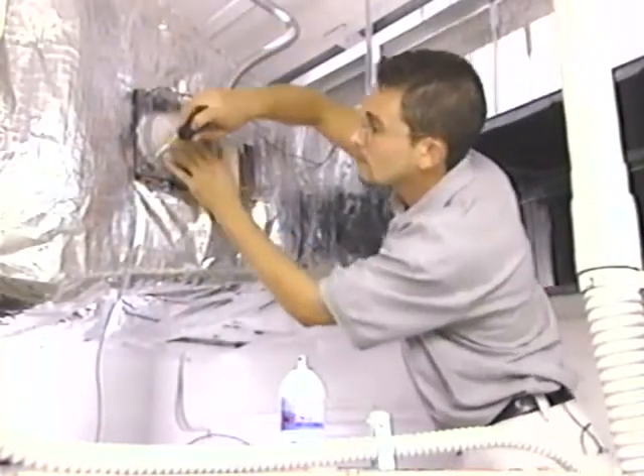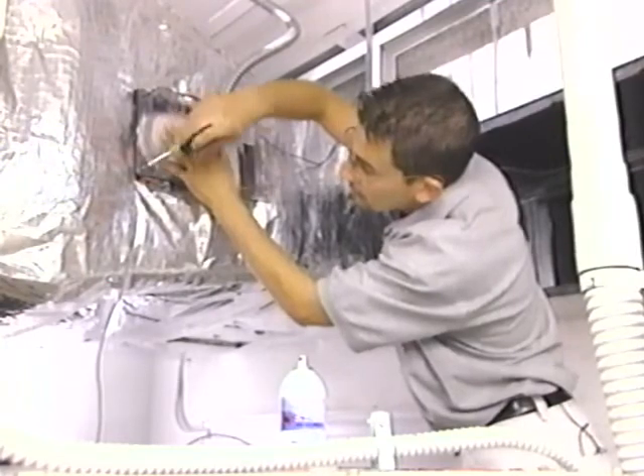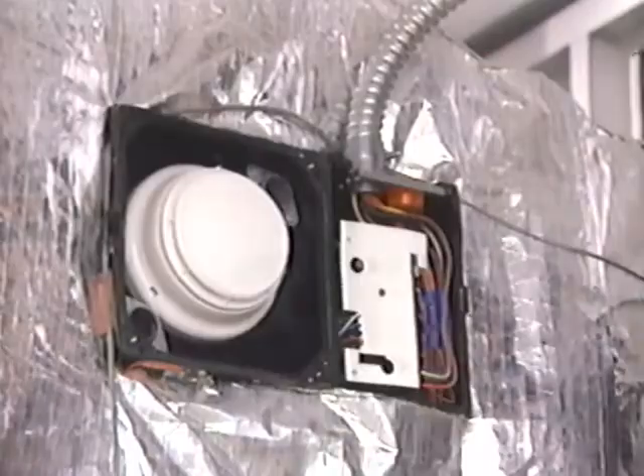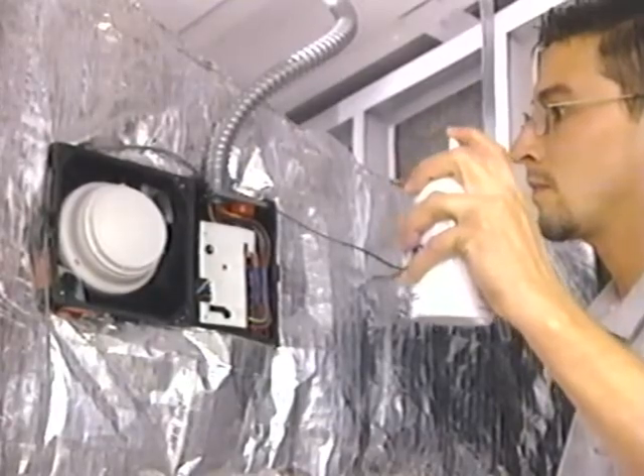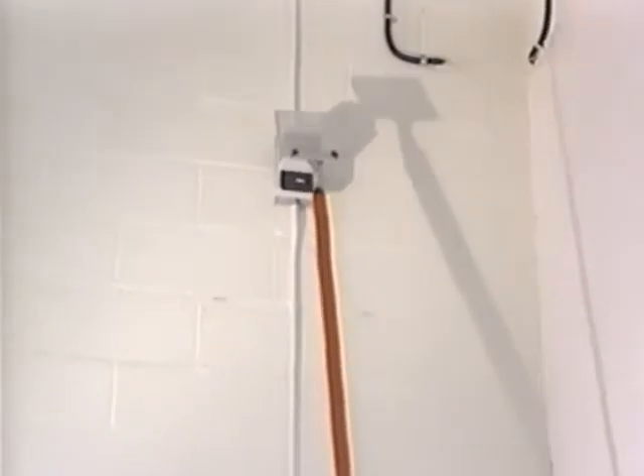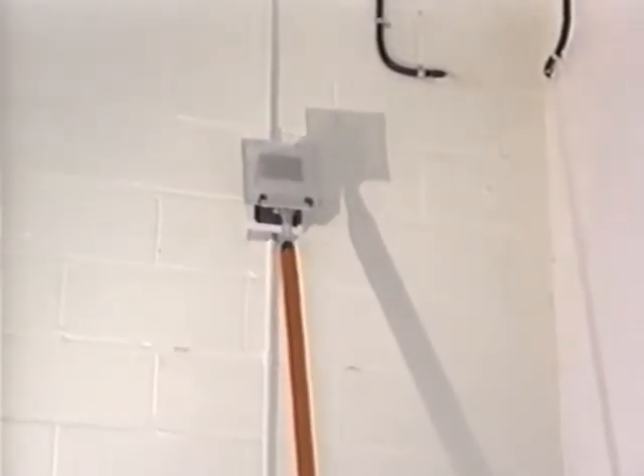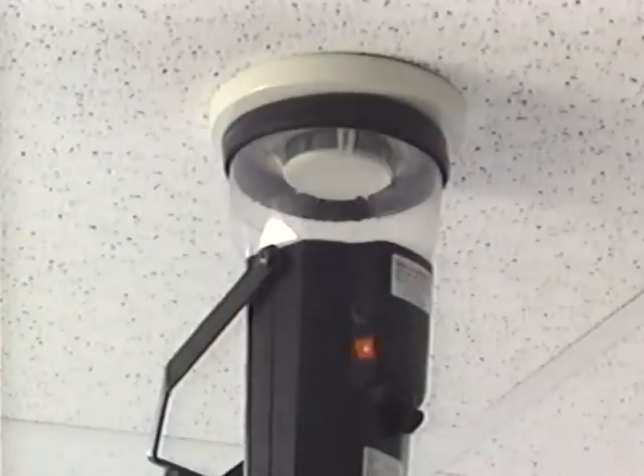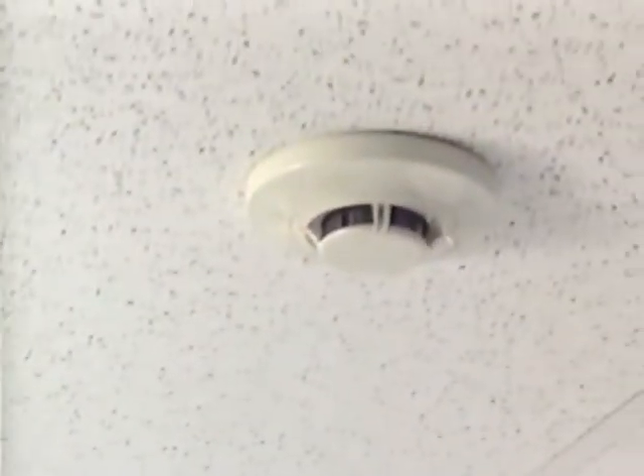Air duct smoke detectors and air sampling smoke detectors should be tested following manufacturer's recommendations — generally functional tests that introduce smoke or aerosol to the detector. Projected beam smoke detectors should be tested with a calibrated card or filter according to the manufacturer's instructions. When an initiating device is a combined smoke detector and heat detector, both elements should be tested independently following manufacturer's recommendations.